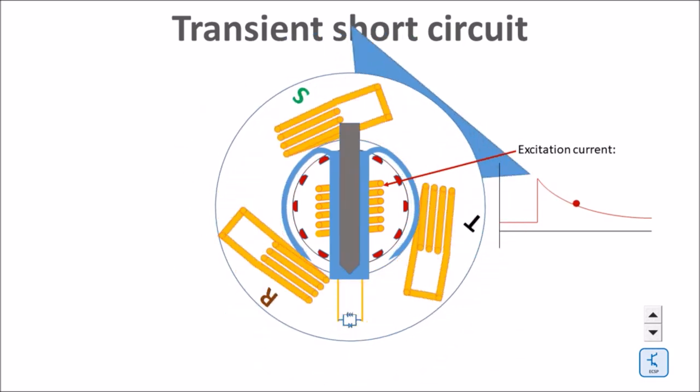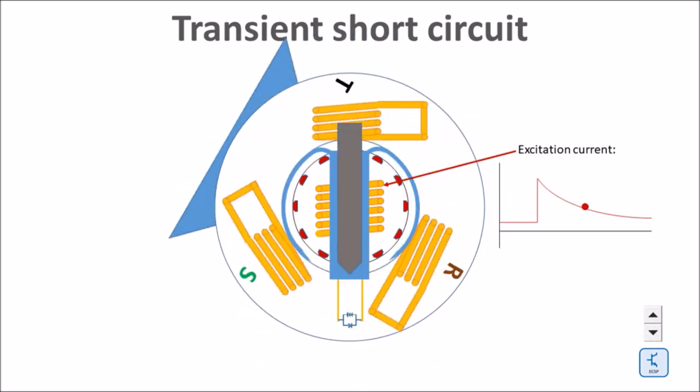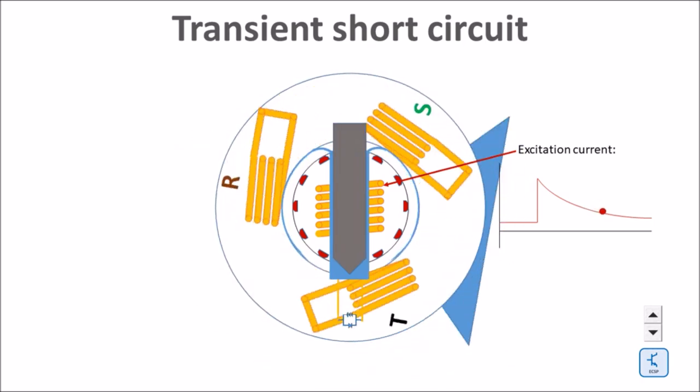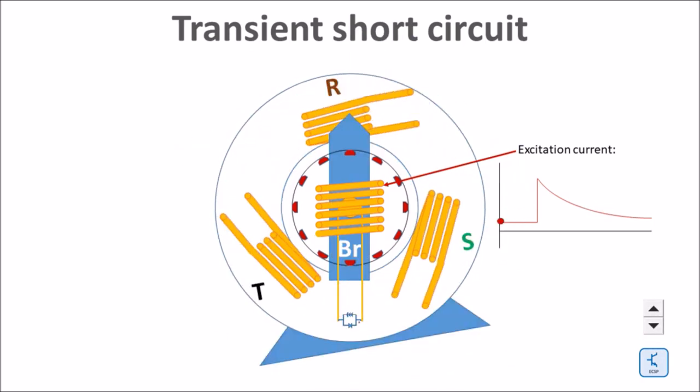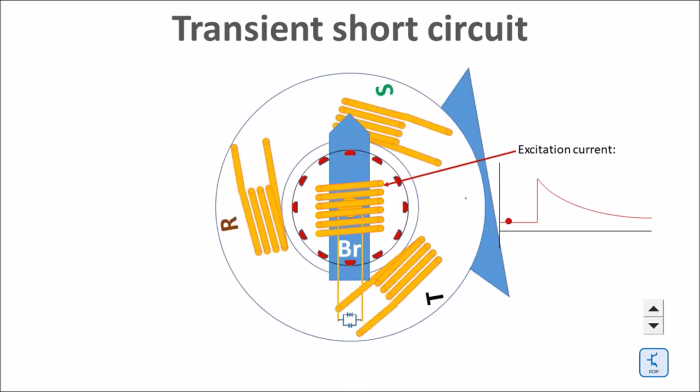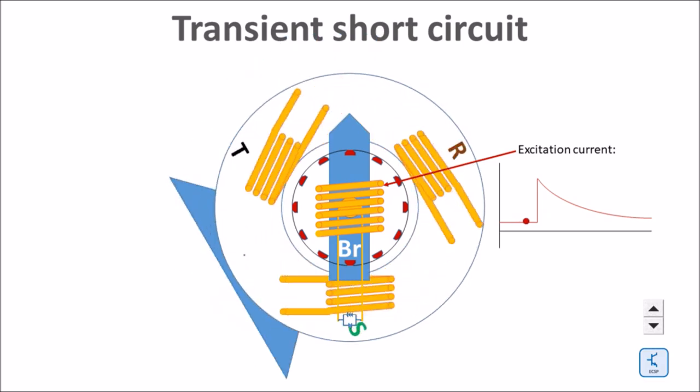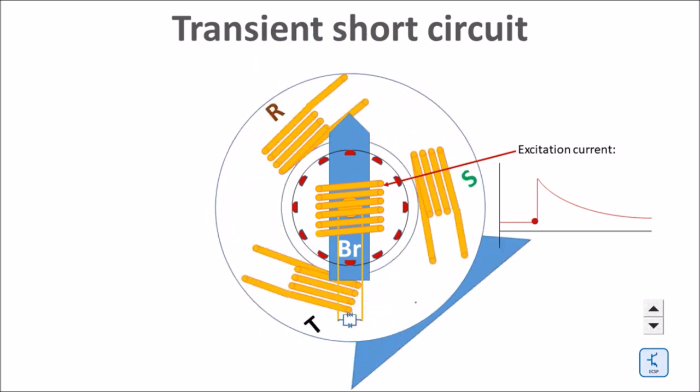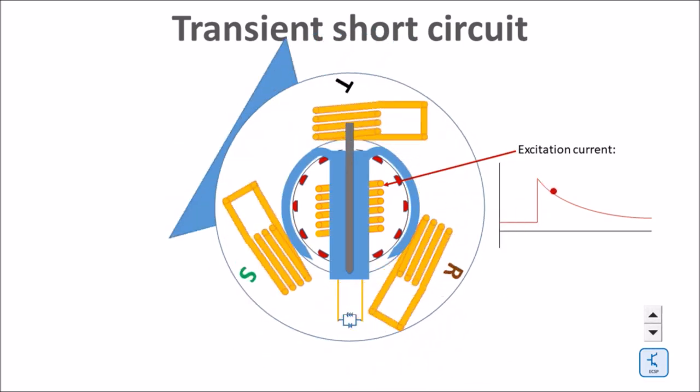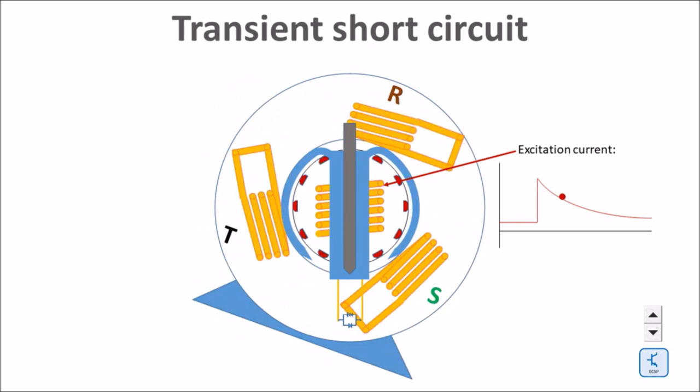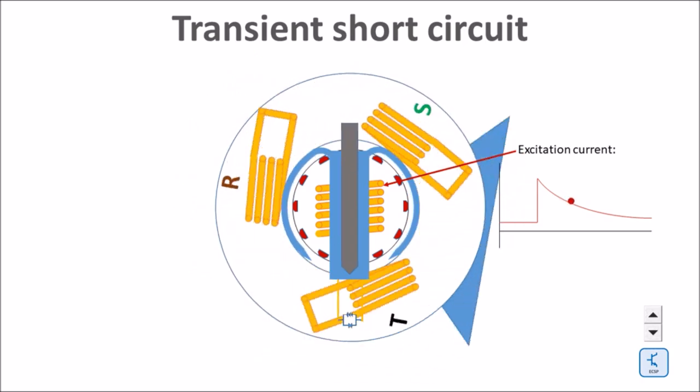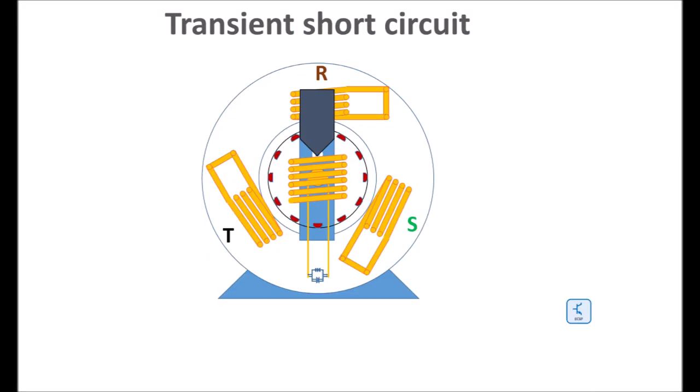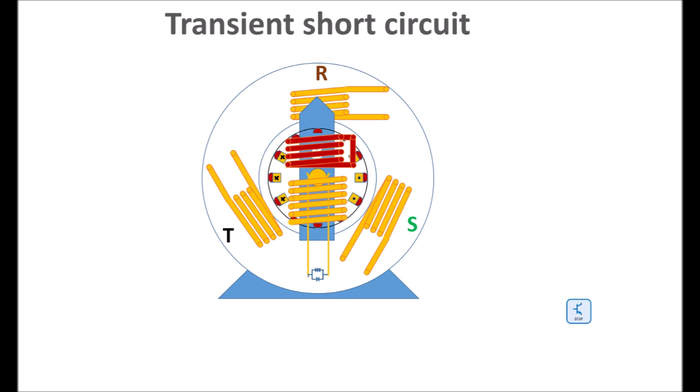The whole process happens within around about 200 milliseconds up to one second. We have two time constants: a sub-transient and a transient time constant. This is due to the fact that there are two coils—we have a damping cage and we have an excitation coil in the rotor.